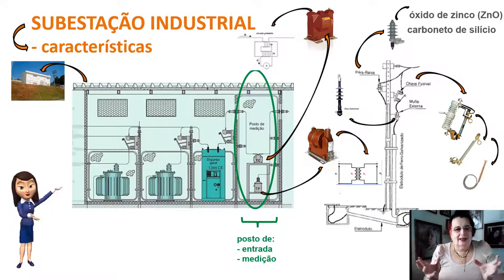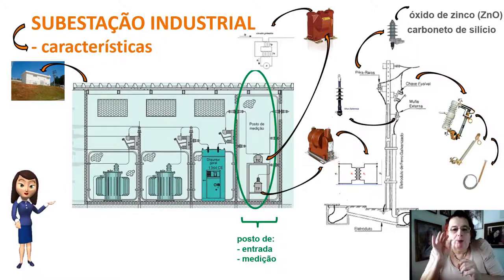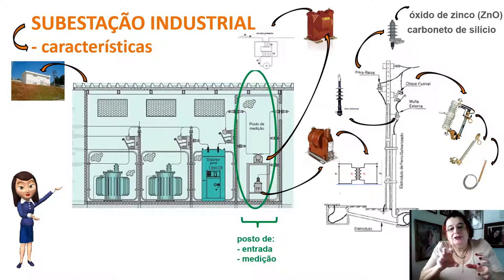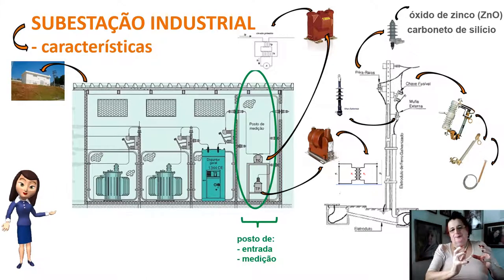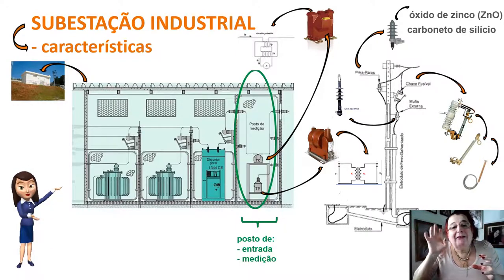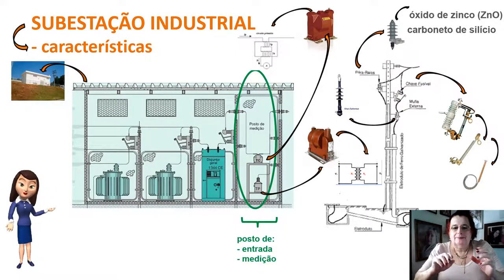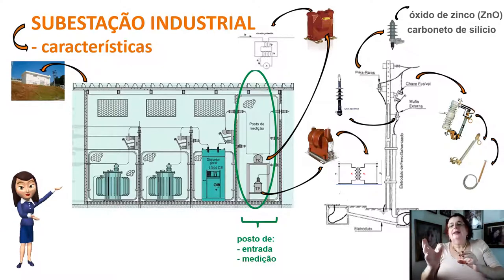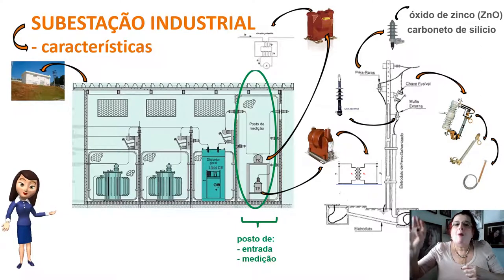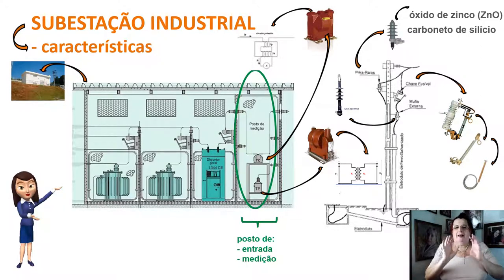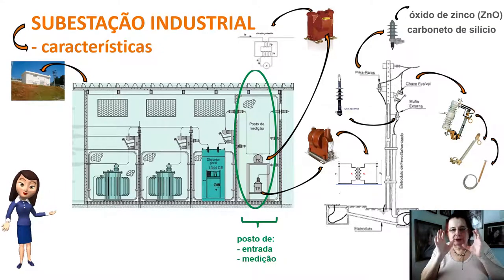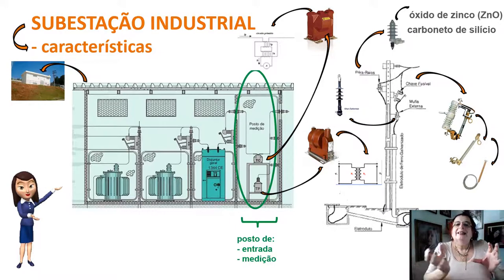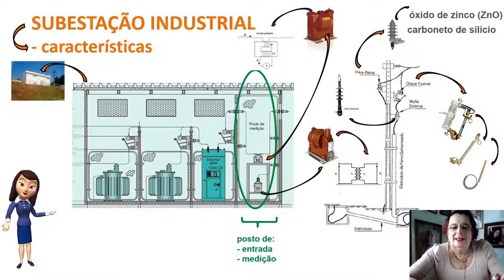O TP recebe os 13 mil volts e rebaixa a tensão para alimentação de outros elementos dentro da própria subestação, e também avisa ao voltímetro qual é a tensão de entrada. Temos também o transformador de corrente (TC), que mensura qual é a corrente consumida pela indústria, alimentando o amperímetro para que meça essa corrente consumida.